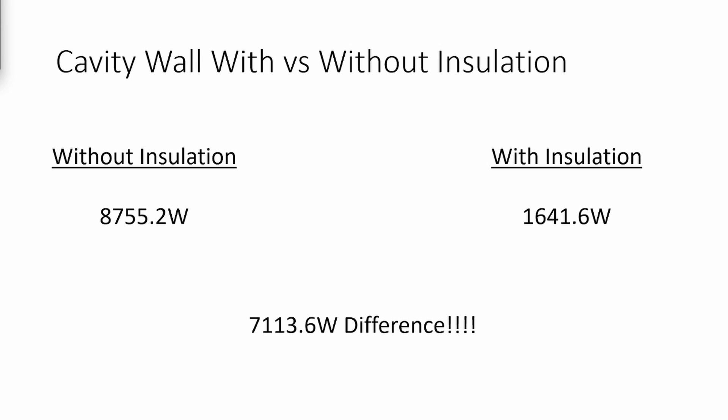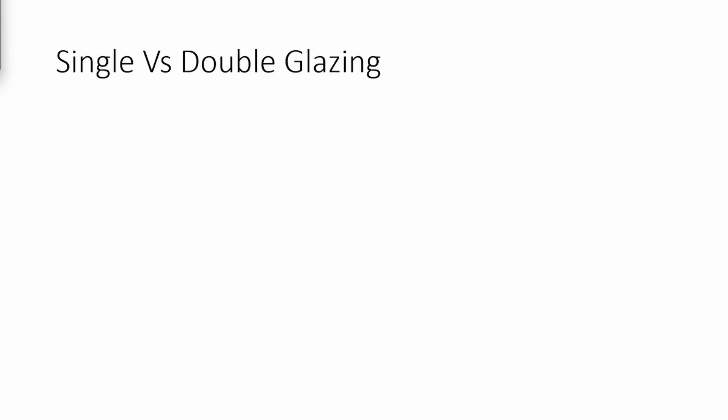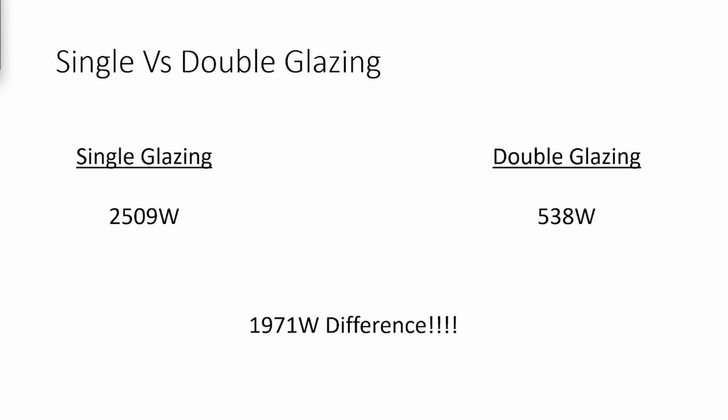We can do the same process with single and double glazing. Single glazing has a U-value of 5.6, and using the heat loss equation, we see that the heat loss would be 2,509 watts. Double glazing has a U-value of 1.2, and from the same equation, the heat loss is almost a fifth, being at 538 watts. Once again, we can see that there is a vast 1,971 watts difference between the two.